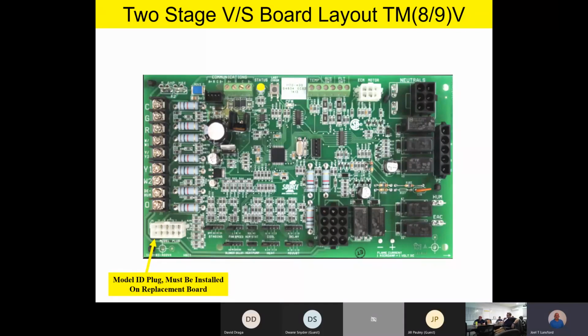Now, it should be noted, all of your jumper selections, your cool and your adjust and your delay, the plug wouldn't remember any of that. This is strictly for a model ID. So this plug doesn't remember any of your jumper settings. All that model ID plug does is configure the board for the size of the furnace that it's hooked up to.